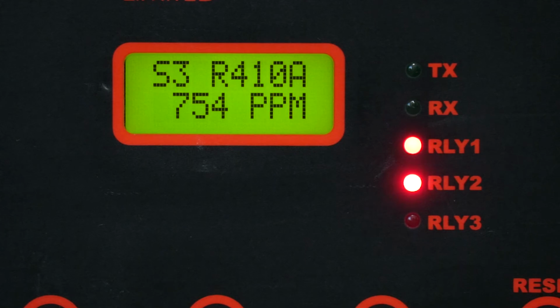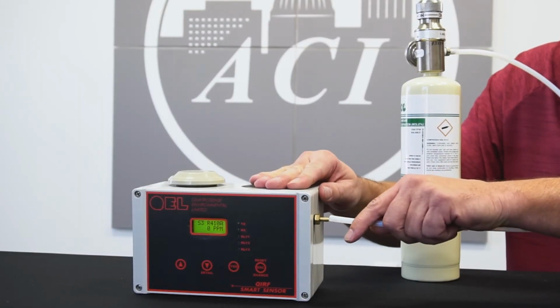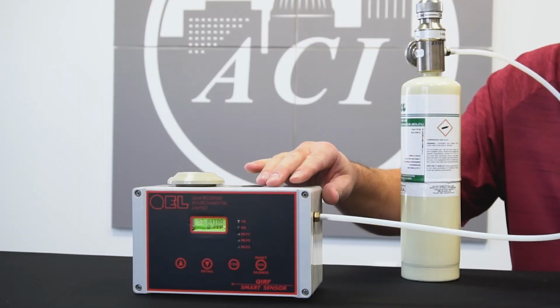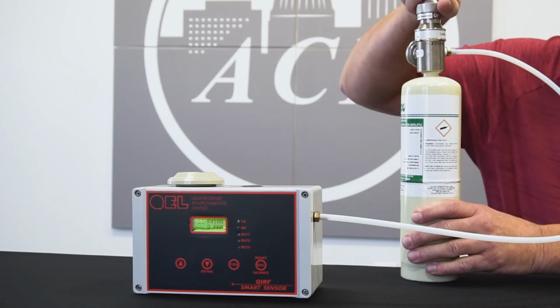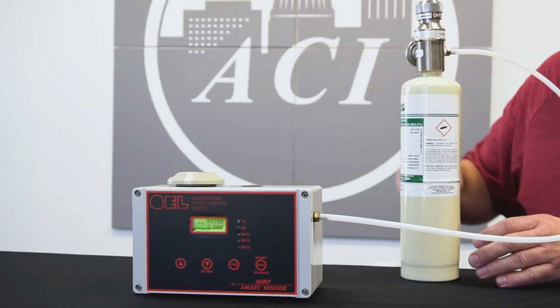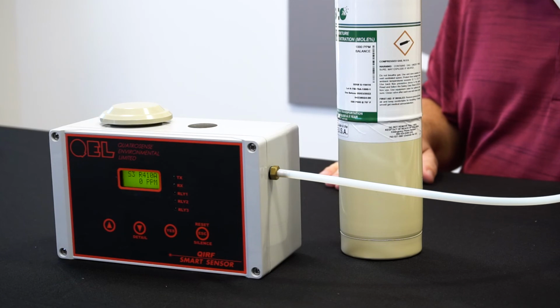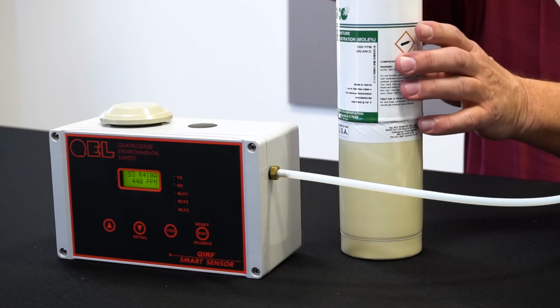to a controller. The QIRF sensor should be tested for accuracy and bump tested for functionality once every year and calibrated if needed. Never use 100% nitrogen gas to perform a zero calibration on the QIRF transmitters. Nitrogen is cold when it leaves the cylinder and has the potential to crack the infrared sensor.